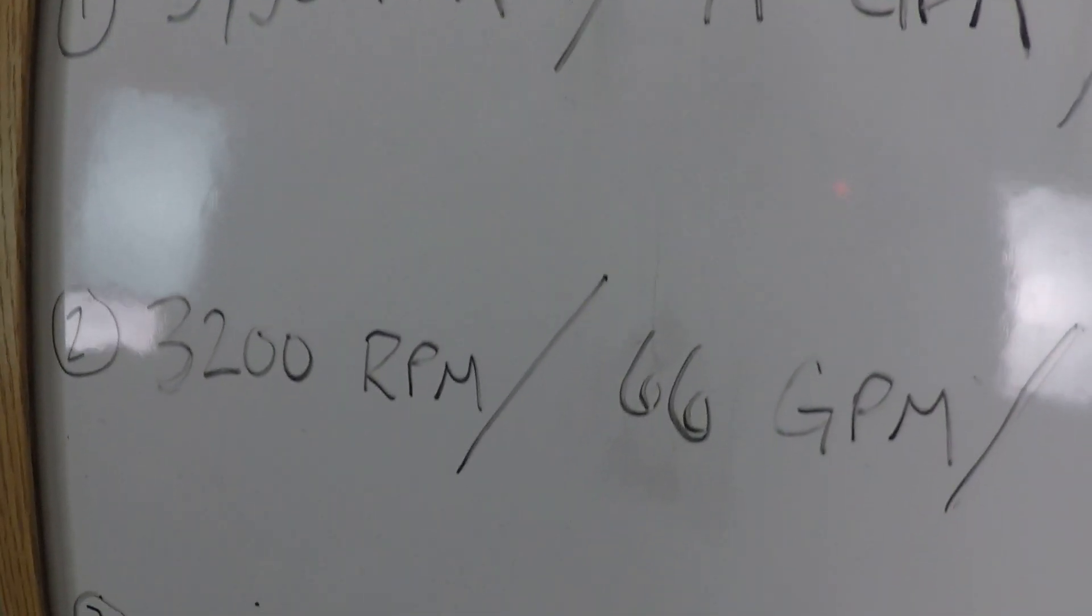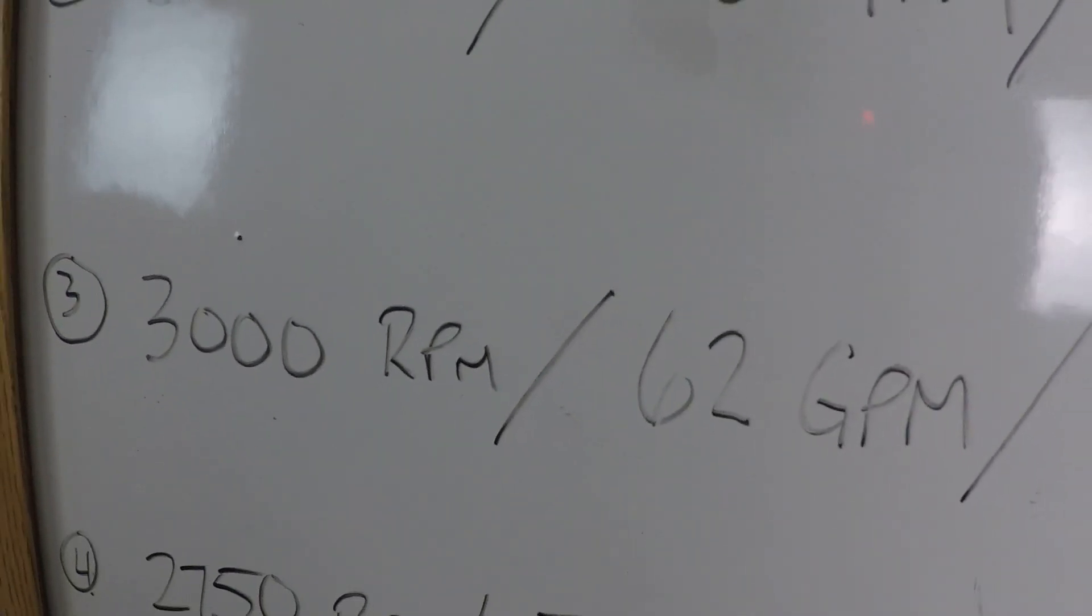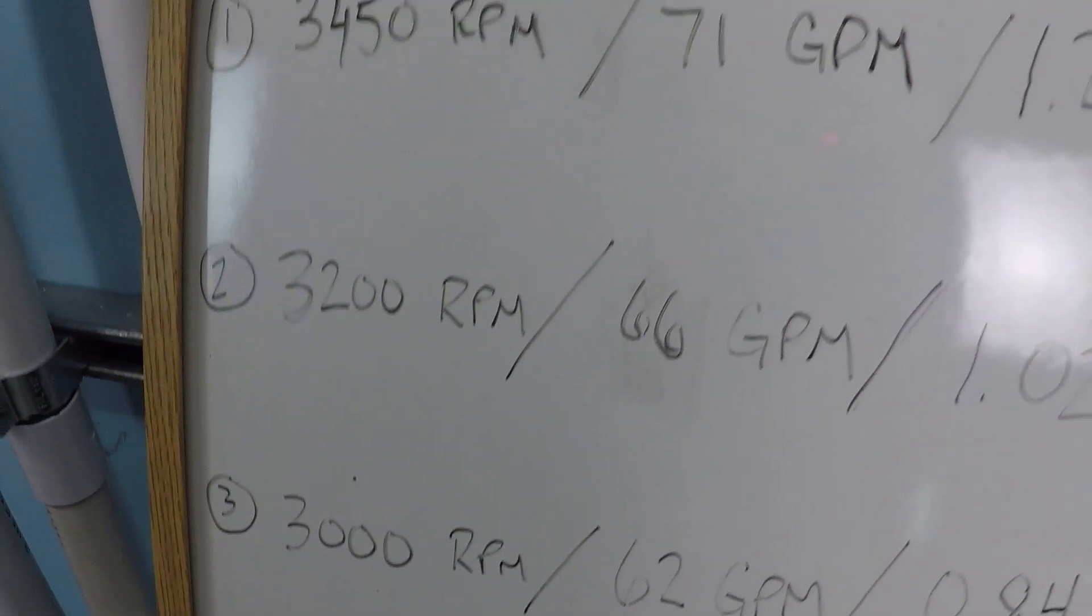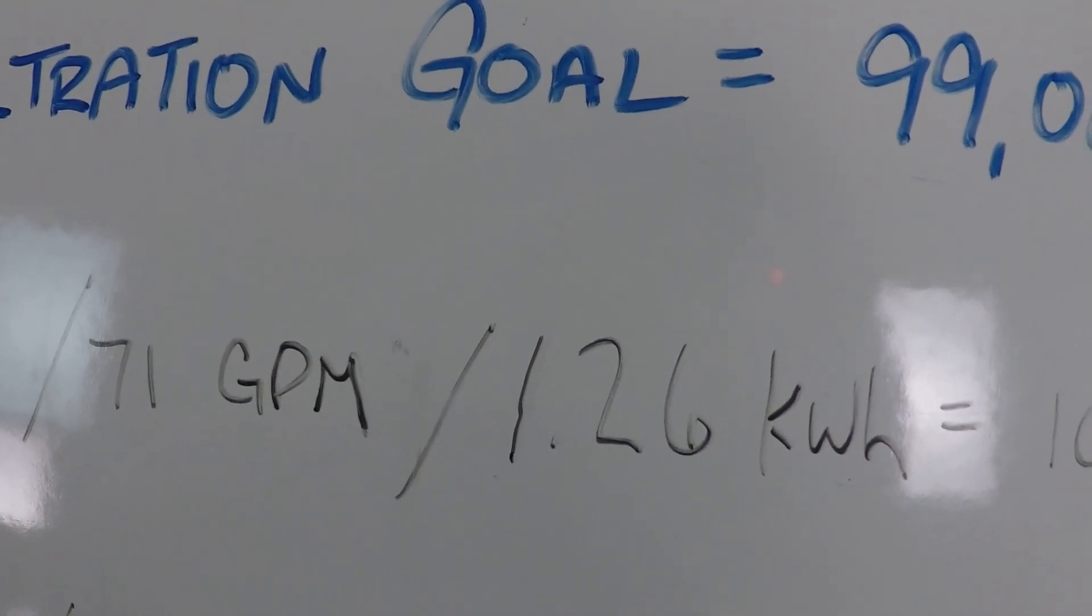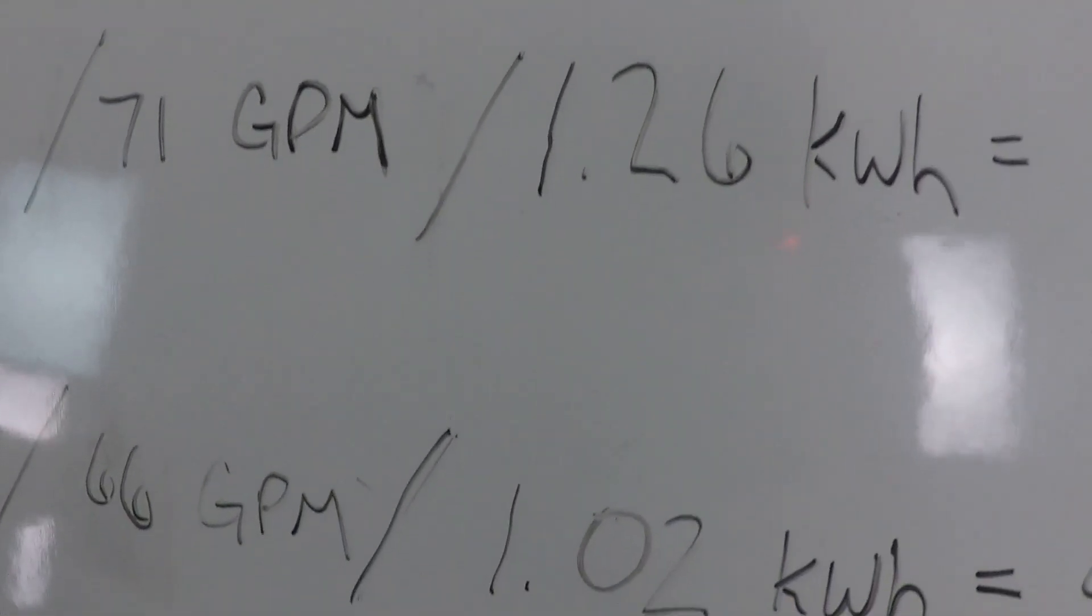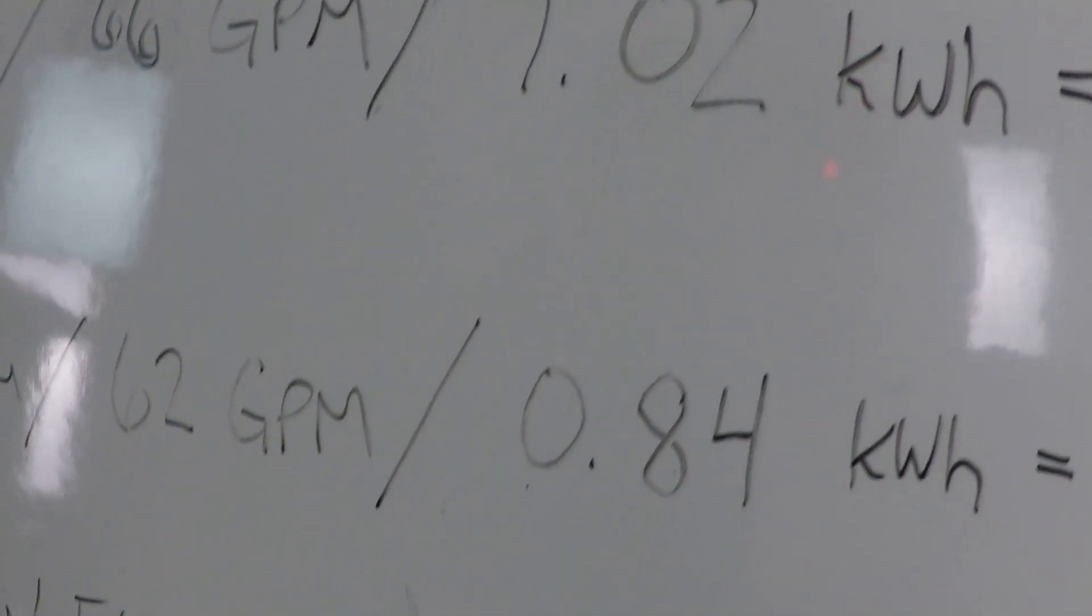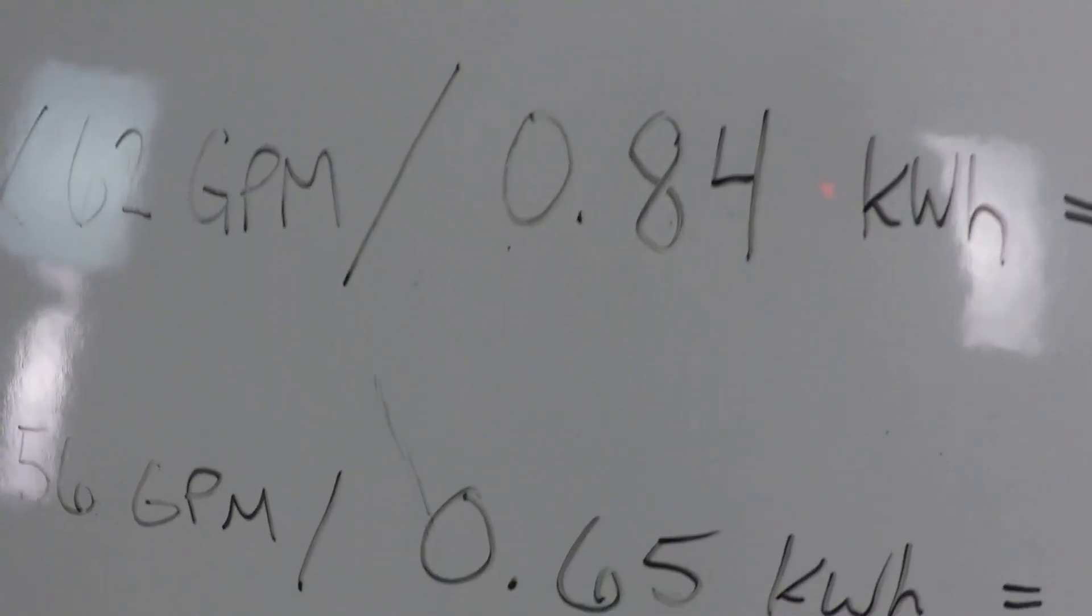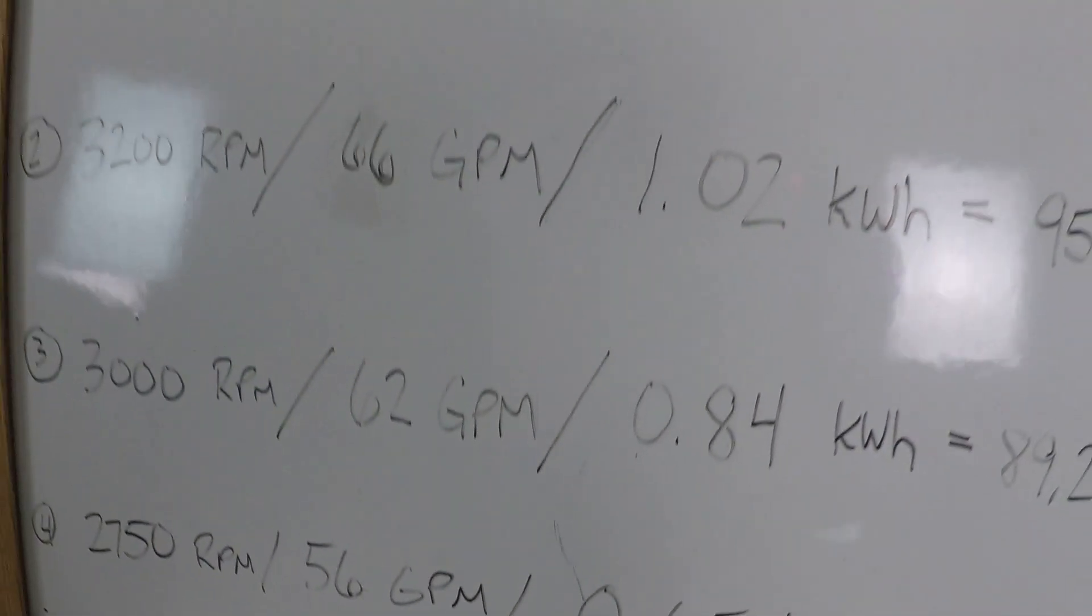71 gallons per minute, 66 gallons per minute, 62 gallons per minute. But the power consumption drops much more aggressively. 1.26 kilowatts per hour, 1.02, 0.84, and 0.65.